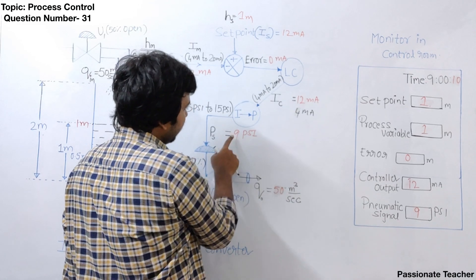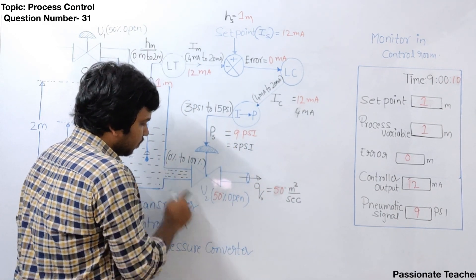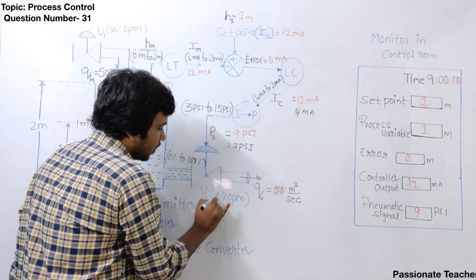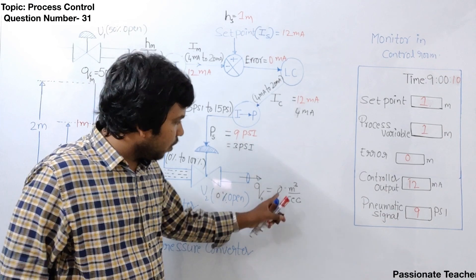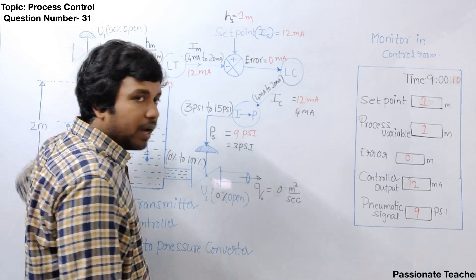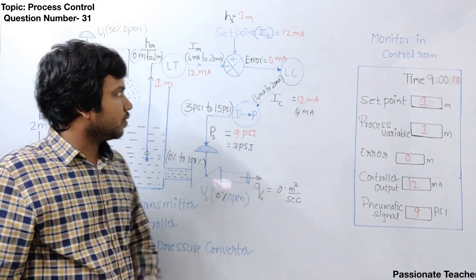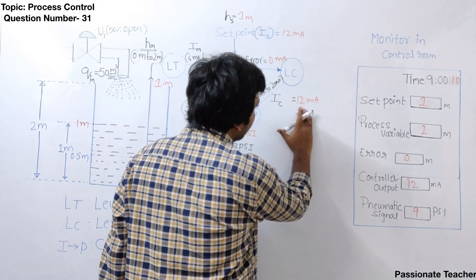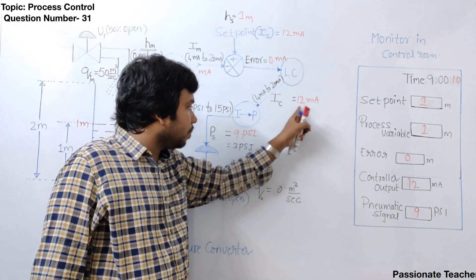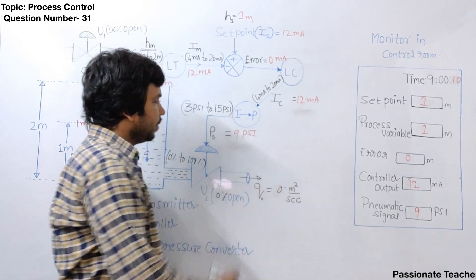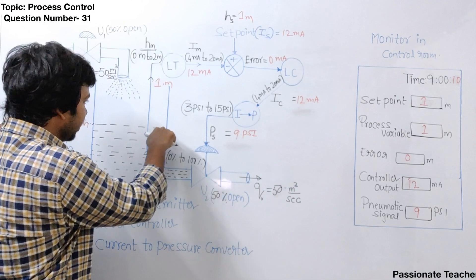If it generates 4 mA, the pressure would be 3 psi, which means the valve is 0% open — fully closed. If the valve is fully closed, the output flow rate becomes 0 cubic meters per second. But the input flow rate is still 50 cubic meters per second, so the water level would jump above 1 meter. This is why when the error is 0, the controller output should not be 4 mA but must be 12 mA — so the valve stays at 50% open, output matches input, and the water level stagnates.